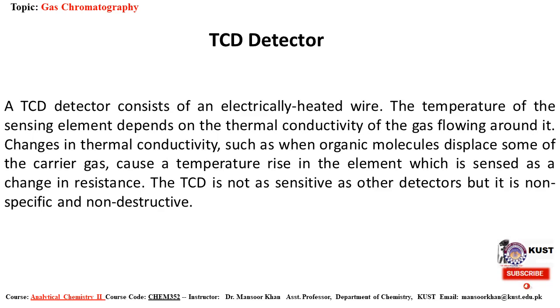The thermal conductivity detector is basically based on change in temperature. The TCD is not as sensitive as other detectors. The problem with it is that it is non-specific and less sensitive, while the advantage of the thermal conductivity detector is that it is universal and non-destructive.